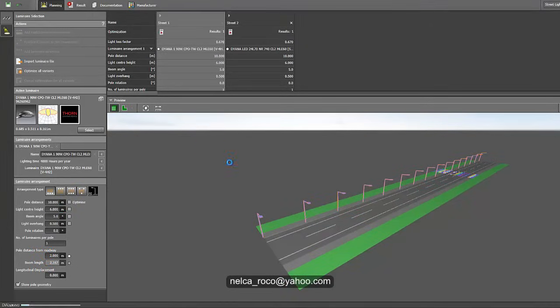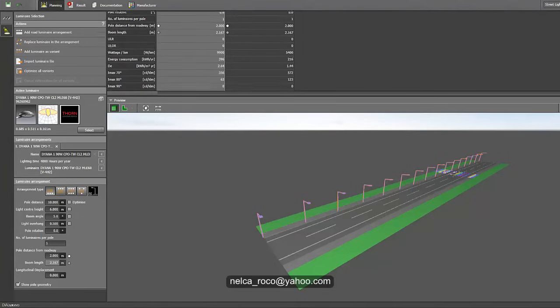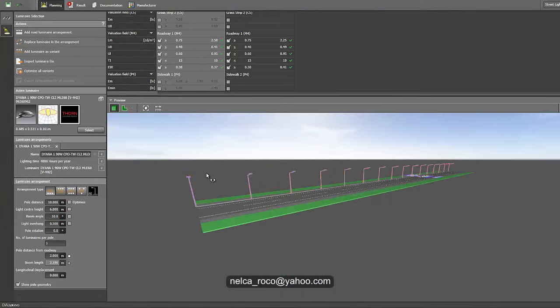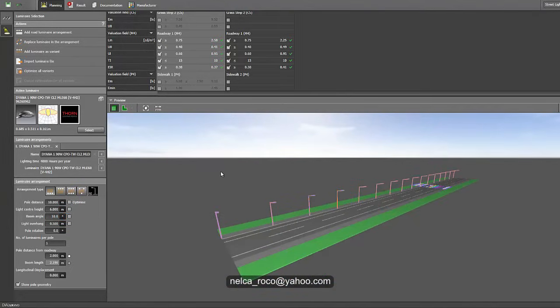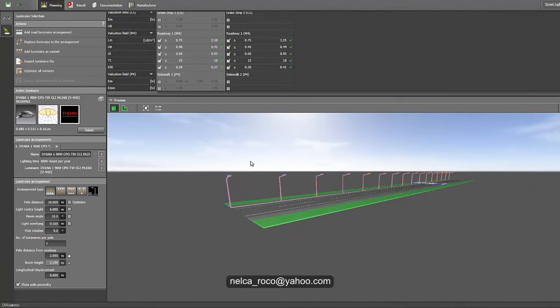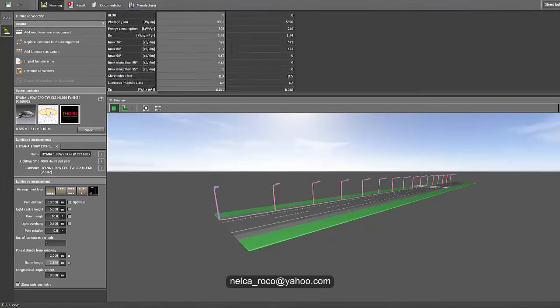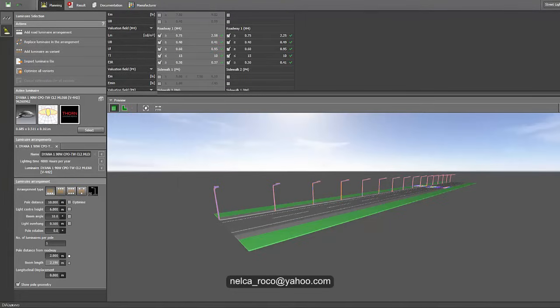Run the calculation — it seems there's a red result. Let's check: we found one red value — it's the overall uniformity at 0.35, but the requirement is 0.40. However, if we change the boom angle to 10 degrees and re-run, it's now fine. By using a lower wattage of 90 watts and a lower pole height of 6 meters, with the required 10-meter pole spacing, we still achieve the lux value — both in LED and conventional metal halide.